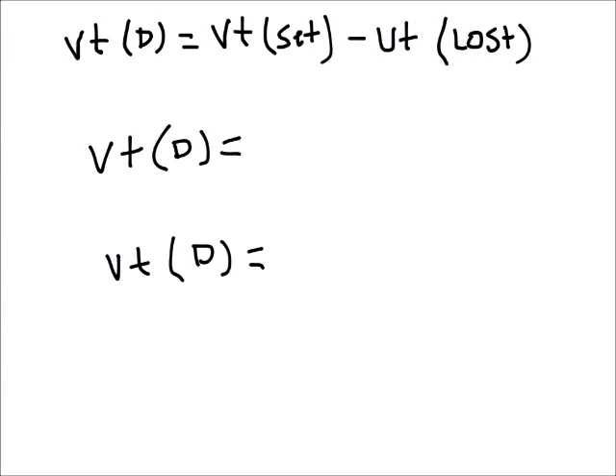Now, let's look at the actual tidal volume delivered. So I'm just putting a D here for delivered versus the tidal volume set. And this is the equation we use to figure out actually how much tidal volume was delivered to the patient versus the tidal volume set. So in this example, we have the set tidal volume of 500 milliliters minus the 50 milliliters that was the tidal volume lost. And this actually equals a delivered tidal volume of 454 milliliters.